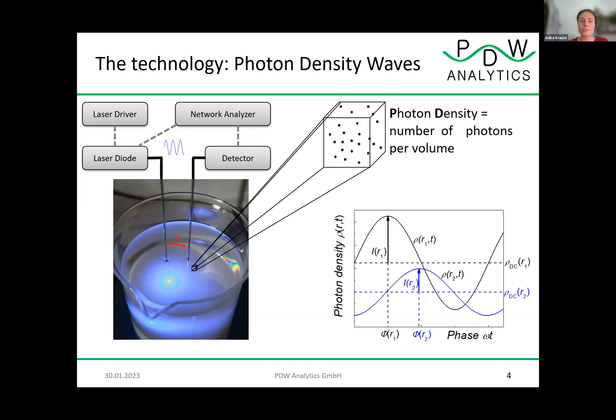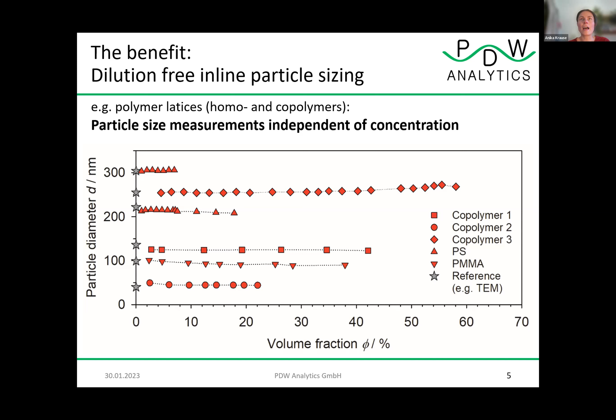characteristics of the material. This is an example I want to show you to stress the advantage that we don't need to dilute our samples before measuring. Here you can see the measured particle diameters of polymer latices in different concentrations, and you can see that we can measure them fairly reliably up to volume fractions of 60%. That's a big advantage compared to standard measurement methods, where you usually can only operate in very low concentration fields, and that then requires dilution in many applications. And if you have to dilute your sample, then it's difficult to do inline sensing, like the live monitoring of a process.